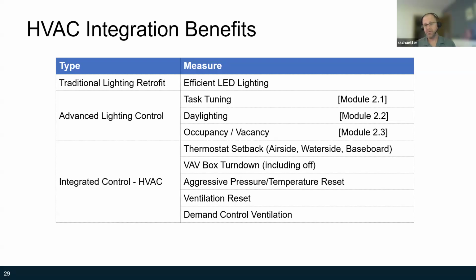VAV box turndown or shutoff will reduce or shut down airflow when an unoccupied signal persists for 5 minutes. Similarly, the air handling unit supply fan can be set to minimum speed or shut down altogether in the case of an unanticipated unoccupied status. Ventilation can also be reset via demand control ventilation to allow for the recalculation of required fresh air via ASHRAE 62.1 and control of the outside air damper position based on the number of zones that are unoccupied.